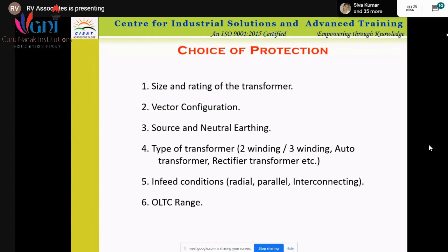There are various types of transformers like 2-winding, 3-winding, auto transformer, rectifier transformer. There is an earth transformer also. If you have a delta connection, in a delta connection you cannot do any earthing. So how do you do the earthing? Then we use the earth winding. That is called earthing by earth transformer, and normally it is used in substations, not in any other places.